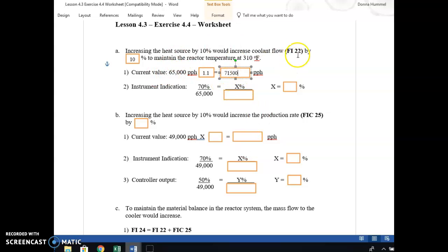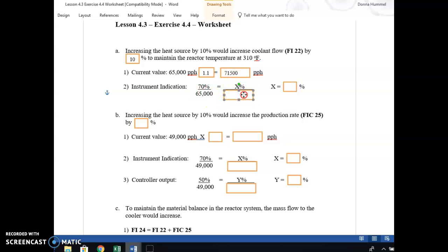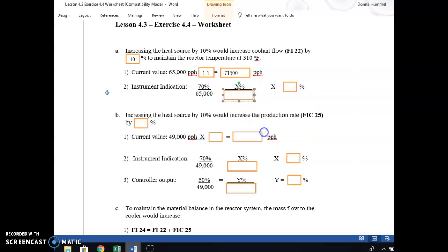Now, FI22 is also a controller output on the instrumentation. So now we just put this new number here. The ratio is we take what is the current number? The current factor is 70% on the indicator at 65. This is the normal operating conditions, but we've upped it, so we have our ratio. This new number is 71,500, so we put that in there, and when we do the math, we find that this number is equal to 77%. So that goes up, which makes sense.